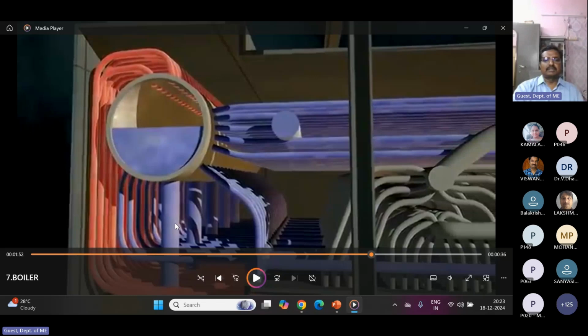So through the water walls, when it receives energy from the flue gases or furnace, after getting heat energy, it will transform into steam. It will not transform directly. What I am saying is about the 2 megawatt boiler. This is a subcritical boiler. It is called a subcritical boiler.